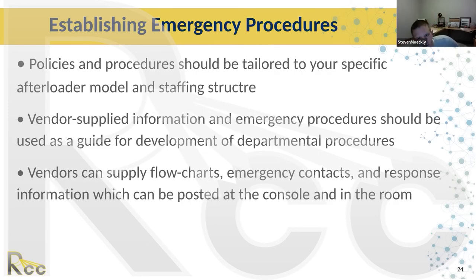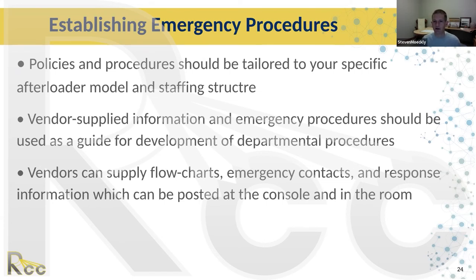Policies and procedures should be tailored to your specific afterloader model — don't take procedures written for a different model, as they may not apply. Vendor information can provide helpful flow charts. You may want to adapt them; some flow charts I've seen were too hard to read in an emergency situation.